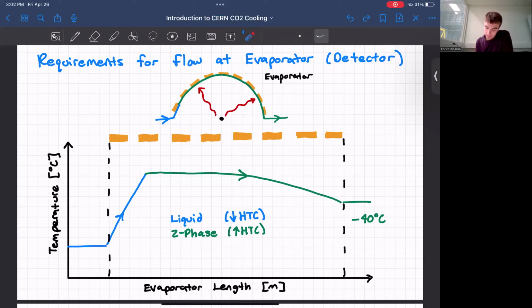Also, I wanted to add that the reason why two-phase is actually decreasing in temperature is because as the refrigerant is flowing along the evaporator, it's dropping in pressure, and the boiling point decreases with decreasing pressure.